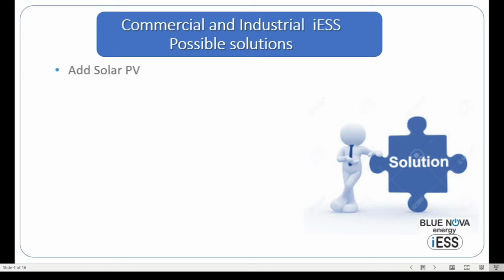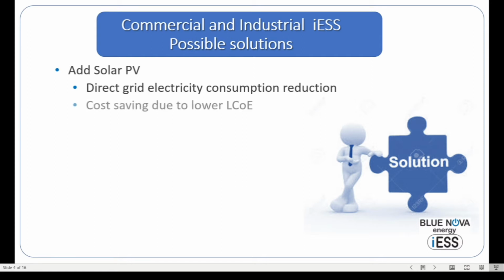So, talking electricity in the modern era, what are the possible solutions? Well, we all know that we can add solar. If you have rooftop, we can add solar PV to the roof. And then we can have a significant reduction, while we're on grid, of the direct energy consumption. We can also see that producing solar, which is in the region of, let's say, 1 Rand to 1 Rand 20 per kilowatt hour, gives a significant cost saving due to the lower cost of energy of such systems. However, those benefits are only applicable for when the sun shines, and we all know that those benefits are really applicable during the time of the day when some of your peak demands are not present.